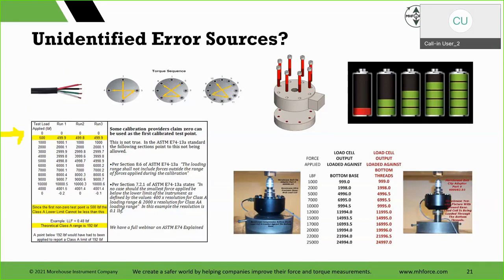Theoretical class A loading range is 192 pounds here, but since 500 was the first point, you can't assign a lower limit below that. That's per ASTM. There are the sections; it's in section 18 as well. Unidentified error sources: there's torque bolting, there's batteries, there's loading profile here. A 3-pound difference on 25,000 from loading it against the bottom, loading it through, versus this. I mean, there are all these considerations, right?